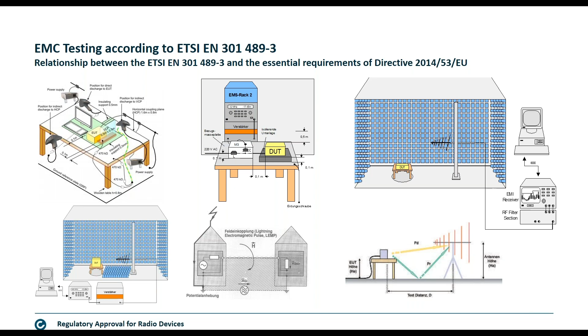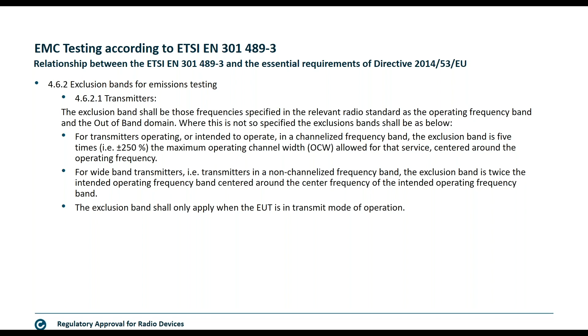We have emission testing here. We have interference testing, meaning your device has been put into an environment where harsh electromagnetic fields are applied to the device. We have indirect surge for devices that have net power supply. And yeah, okay, this should just be an overview that EMC testing is also required for your device. It's important to know that for emission, we have an exclusion band. So your device operates at 868 megahertz, and it operates here at 14 dBm at the maximum power. If we would stick to standard levels of limits given in the standard 301.489-3, then you would hit the limit definitely if your device transmits during the regulatory approval EMC testing.